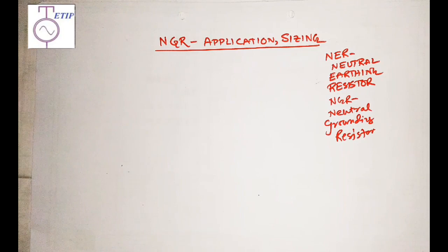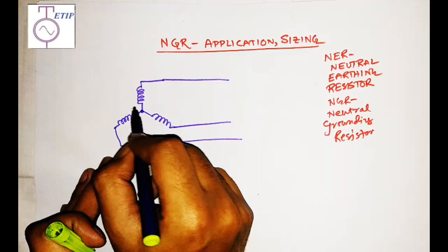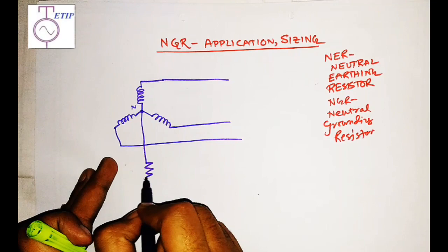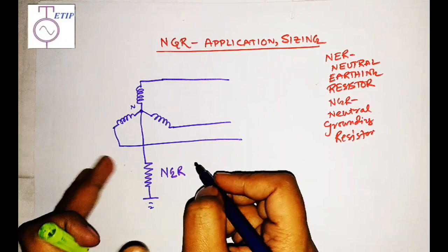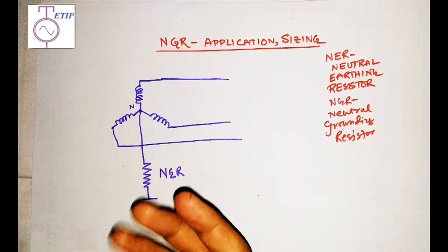NGR is connected to the neutral of a transformer or alternator — for small alternators, not for huge power plant generators. The secondary of a transformer has three output terminals, and the neutral point is connected to earth through an NGR, or Neutral Grounding Resistor. This NGR is required simply to limit the earth fault current.